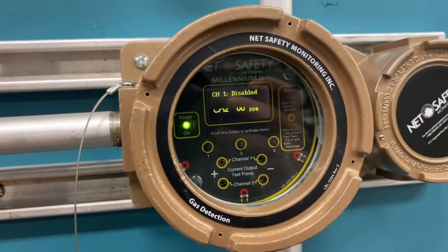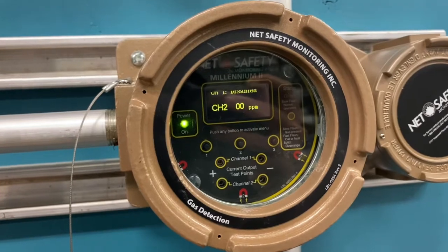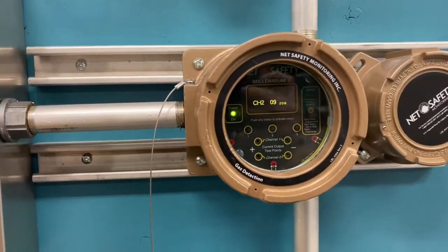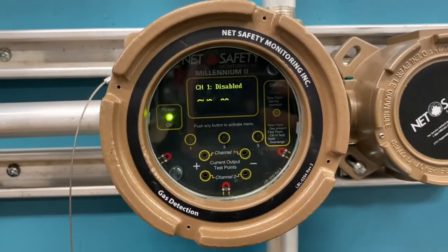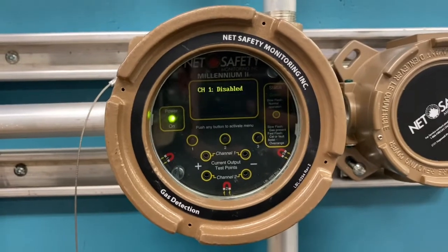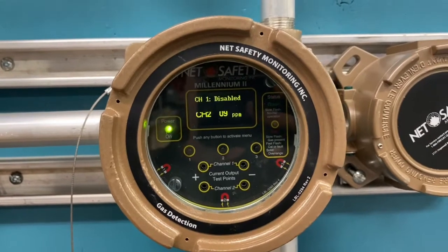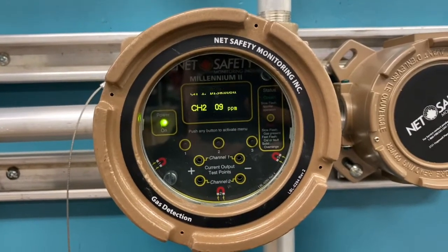I want to see if the sensor's drifted at all. This unit probably hasn't been calibrated in over a year and that's long past due for calibration. I've just introduced our 10 PPM H2S and you can see it's coming up. It's probably been about 30 seconds and it's up to nine PPM right now. We'll wait just a couple more seconds to see if it hits 10. Then we'll do a calibration. It responded fairly quickly. It looks like we're pretty well leveled out at nine. What I'll do now is we'll go ahead and do a calibration.